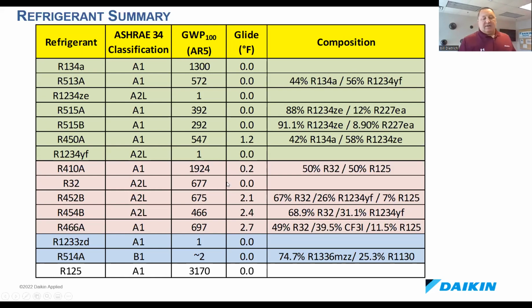And the temperature glide basically is just a measure of how much a blend will fractionate or separate if it's in a pool of boiling, right? Because the refrigerants will boil off differently with different vapor pressures. And as that evaporating temperature changes over the course of boiling that pool, the amount of change is what's called the temperature glide. And the higher that changes, the more volatile the mixture is.